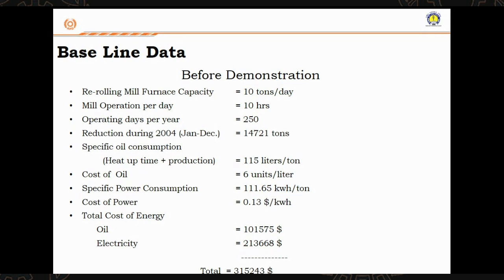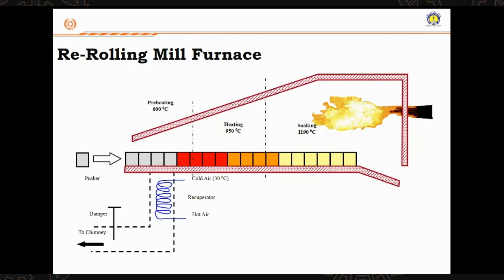14,721. We have a specific oil consumption, we have a specific power consumption, and the total energy consumption of the plant. So what happens is you have the metal coming here. It is like a pre-treatment. It is preheating, then it is entering into the furnace. It gets heated up to 950, and it will be soaked for some time, and the product is being removed.